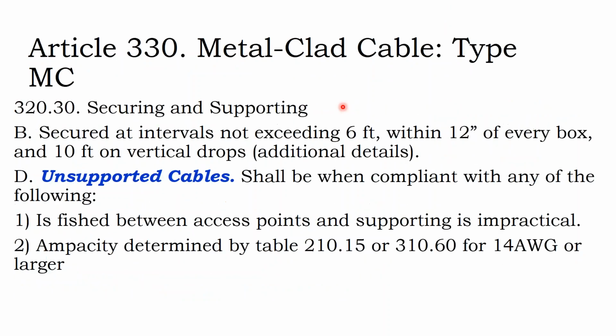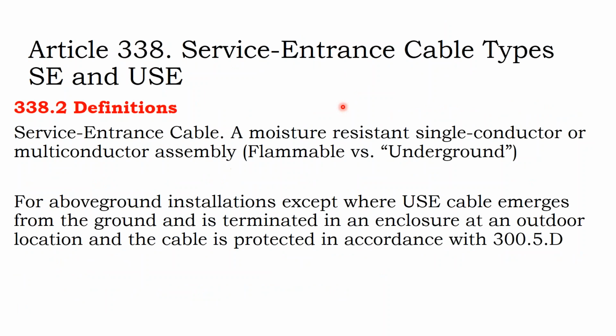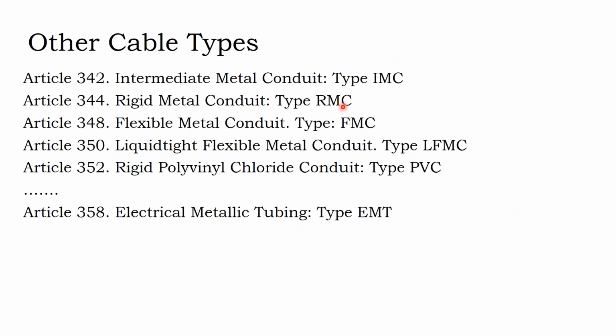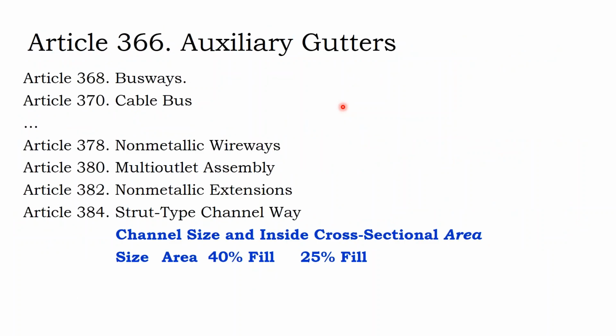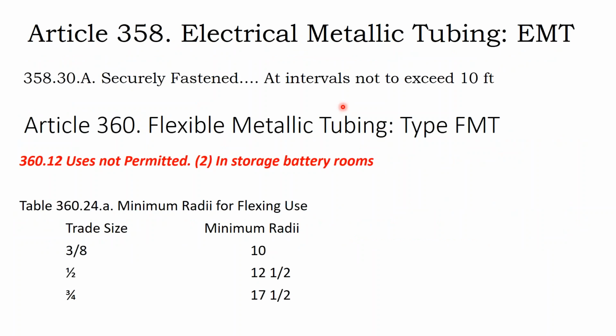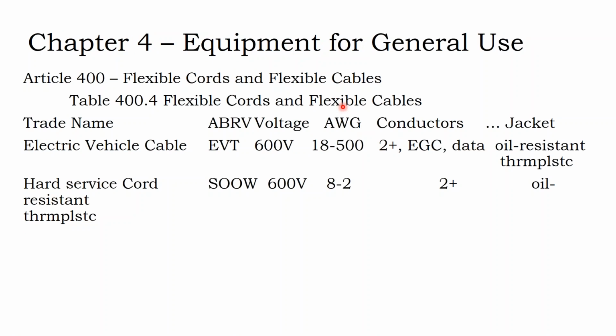Let's see. It's common to use USE-2 cable up on the rooftop as solar cable. It's a service entrance conductor, but it's a very robust service entrance conductor. One thing not to forget is that with tubing, it has a minimal bending radius. So if you get into larger and larger conduits, you need to leave yourself more space in the control room for bending that wire.